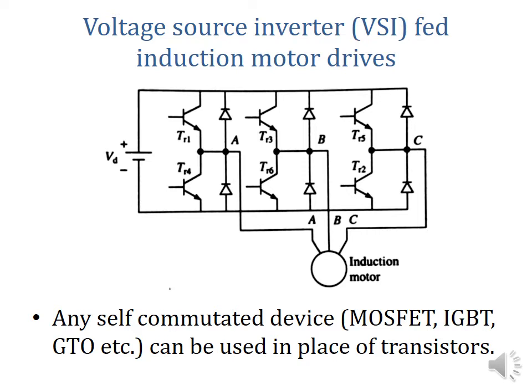This is the basic circuit diagram of a voltage source inverter fed induction motor drive. In this circuit, the input voltage is a DC voltage equal to VD, and it uses six switching devices TR1 to TR6. Instead of using transistors, we can use any other self-commutated devices like MOSFET, IGBT, GTO, etc., depending on the power and voltage level.